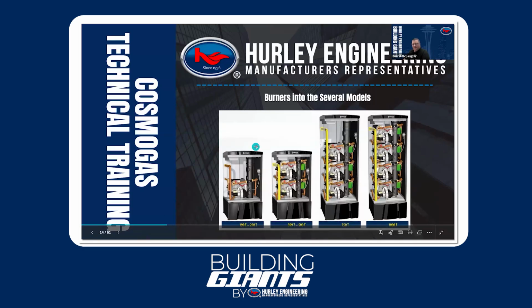Now, this is a picture of a side view of all 4 boilers and what the possibilities are. But mainly I want to show you the motorized valves. You can follow my cursor. You can see they'll put them on each one. So a single heat exchanger unit, obviously you don't need one because there's only one heat exchanger. But the rest of them, we can put motorized valves. And what this does is prevent flow through heat exchangers when they're not in use. So that's an upgrade in efficiency.